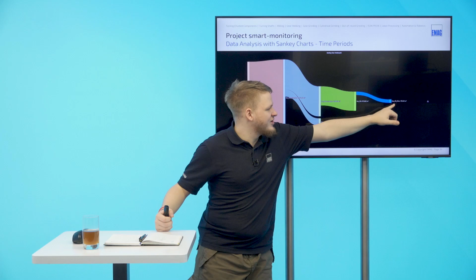Let's now look at our gas system. It's a bit different from our electricity system because it's mainly one big cascaded line, so our gas meters sit behind one another. The last one is our oven in the powder coating department, situated right behind the main meter of that department. Before that is the meter of the entire factory part, and the total factory you can see on the left, distributed so you can easily see that just a small part on the right is actually going into production, into the oven. The rest you see here is 90% just heating. In summertime, that chart mainly goes to one small line, so you can easily spot if you have gas draw anywhere else.